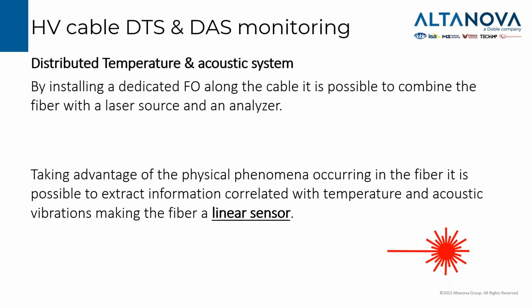Instead, when we move to distributed temperature sensing and distributed acoustic sensing, we take advantage of a specific fiber optic installed along the cable or embedded in the sheath of the cable. Such fiber is combined with a laser source and an analyzer. By taking advantage of the phenomena occurring in the fiber optic material, it is possible to study the response of this material to the laser source thanks to the analyzer, and we can have the whole fiber optic as a unique linear sensor, so we can address each position of the cable with a very low uncertainty, in the meters range.